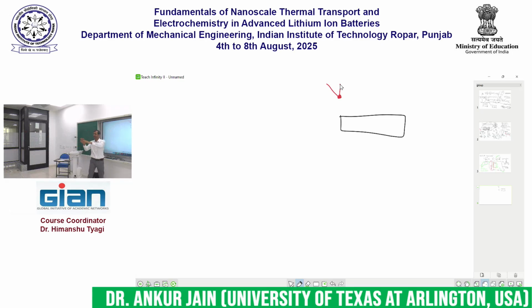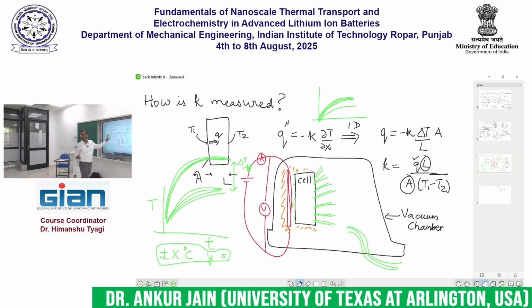In fact, let me take a step back. Do you even use a thermocouple? Or is there something better? Is there a better technique for measuring temperature that would serve you well instead of a thermocouple? Sorry? IR camera, sure. So going back to the previous sheet, an IR camera has certain advantages. What is the key advantage of the IR camera? Yes, it is not in contact.